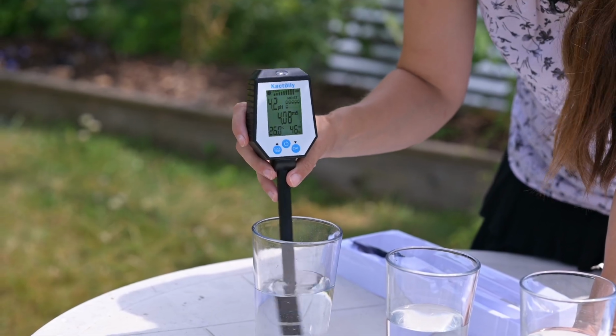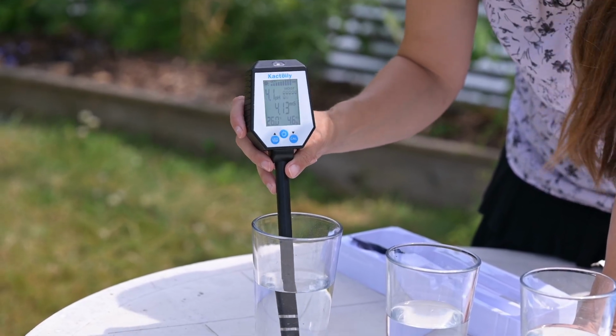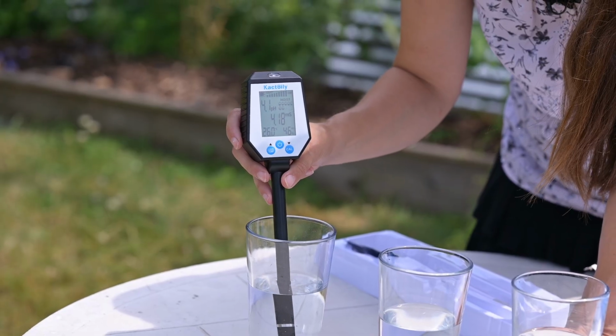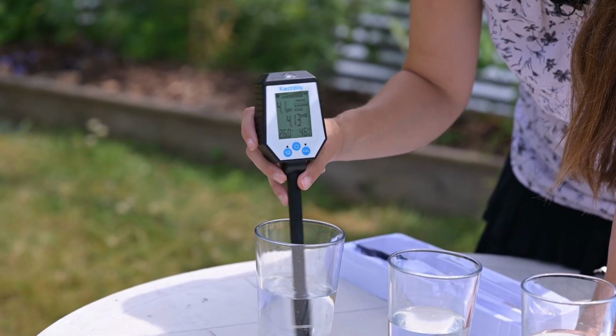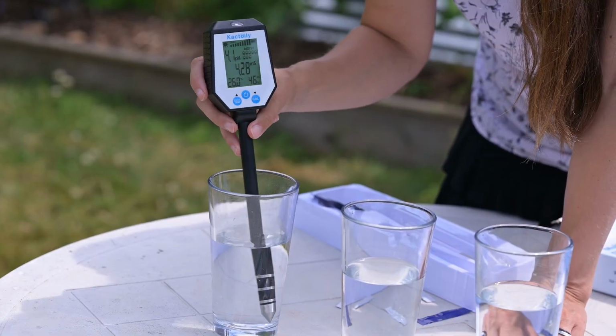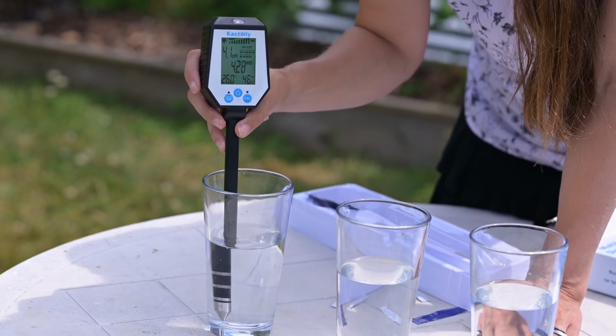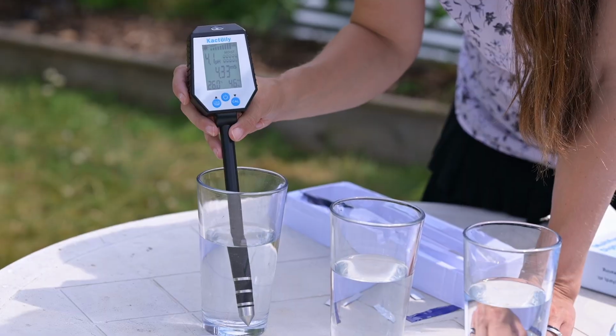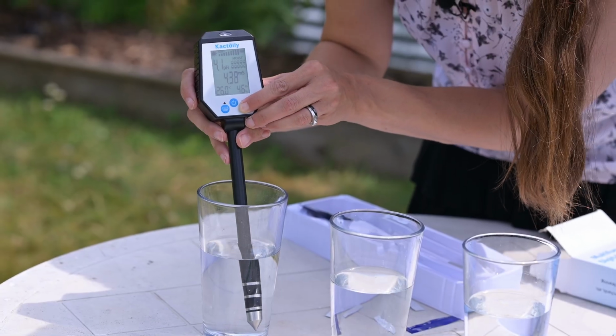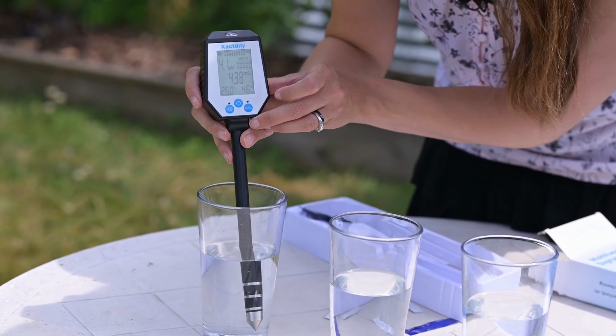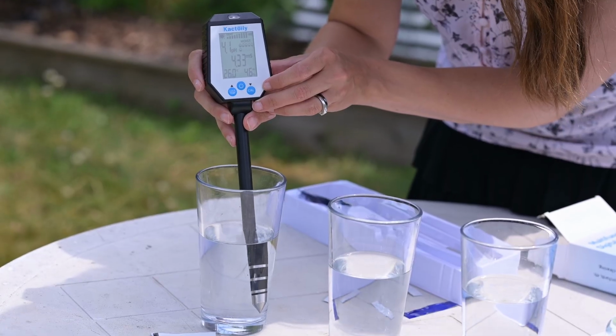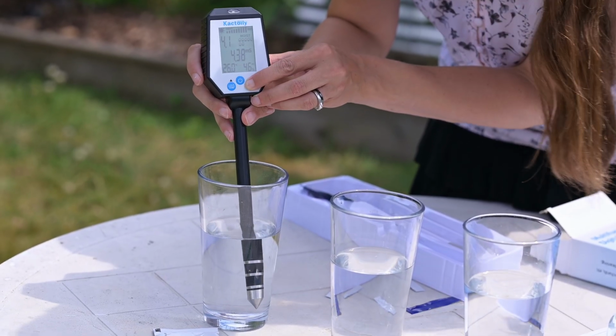You're stable, you should be a 4.1 at the most. Oh, there's a 4.1. Okay, see if it goes down to a 4.0. It has lots of dissolved salts. Doing a great job of testing this calibration solution. Oh, really? Okay, we're gonna hit calibrate, and it's gonna blink for 2 to 3 seconds after the pH blinks.